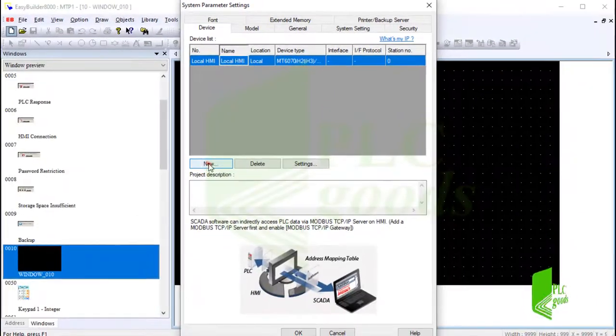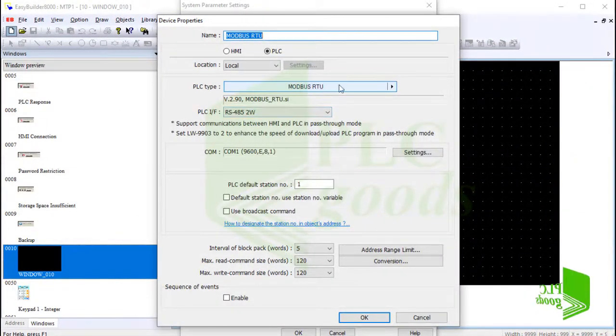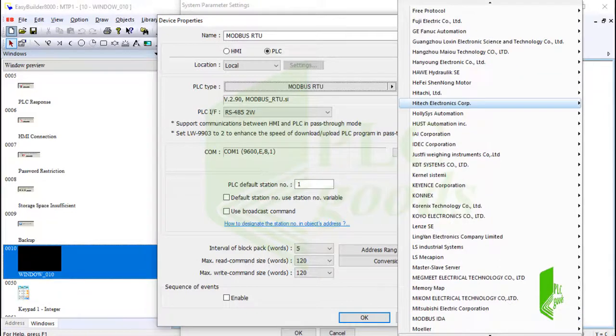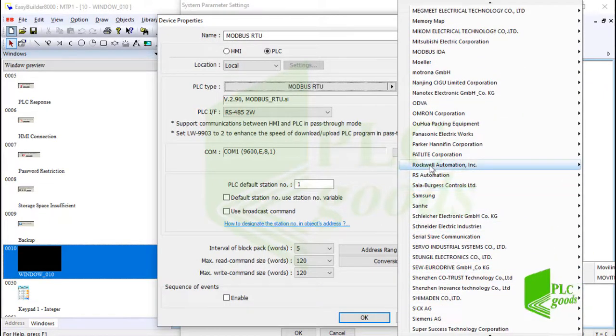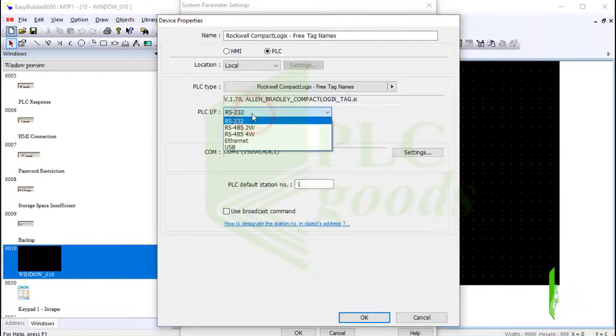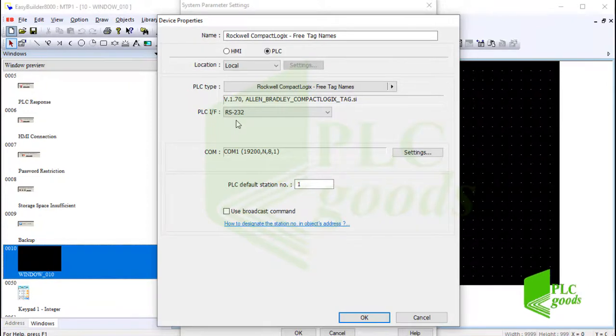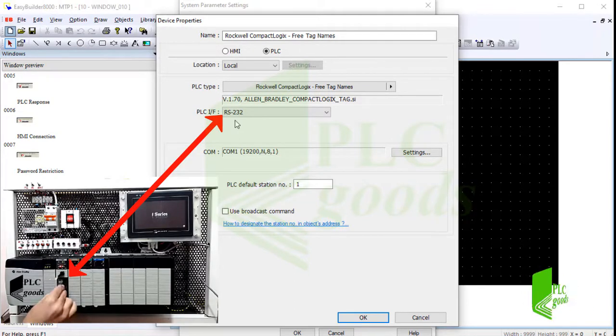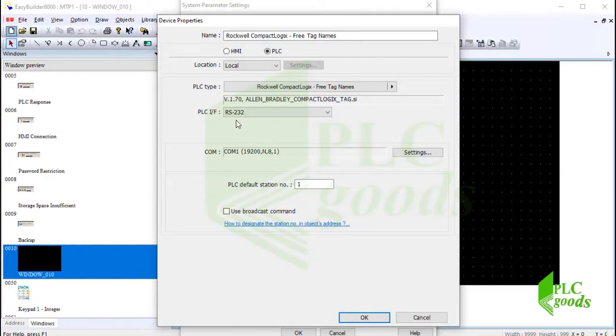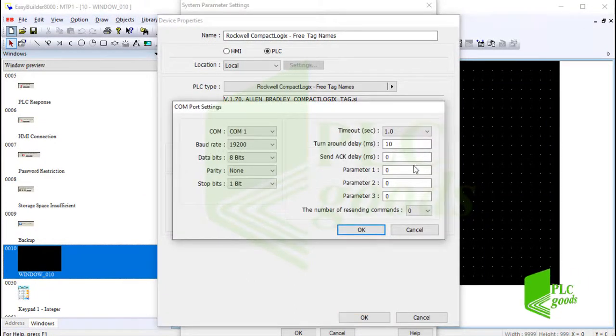Now let me create a connection between my HMI and PLC. Here is a list of different types of PLCs from a vast number of manufacturers. Based on my PLC, I go to Rockwell Automation and select the first choice. Here I determine the connection type between my PLC and HMI — I'm using a serial cable, so let's select RS-232. Note that my CPU has a serial port. The connection settings can be modified, but let's use the default settings.